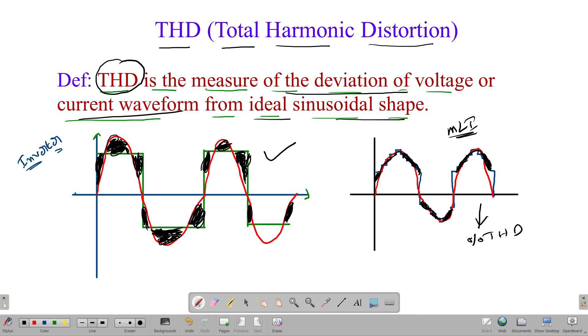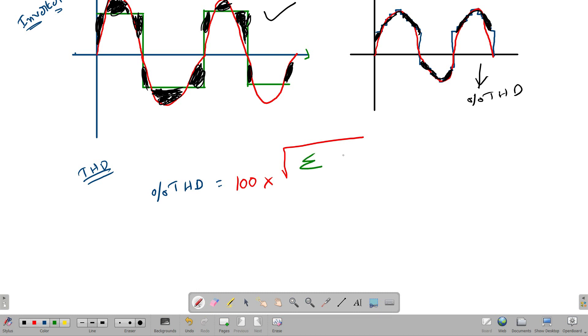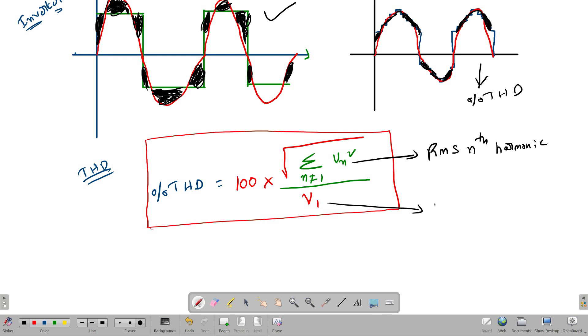The main reason to find the THD is to know the quality of the output waveform — it quantifies the sinusoidal nature at the output. Based on the THD percentage, we can tell the quality of the output. THD is measured using Fourier analysis and is always expressed as a percentage. The formula is: THD = 100 × √(ΣVN² for N≠1) / V1, where VN is the RMS voltage of the Nth harmonic and V1 is the RMS voltage of the fundamental frequency component.